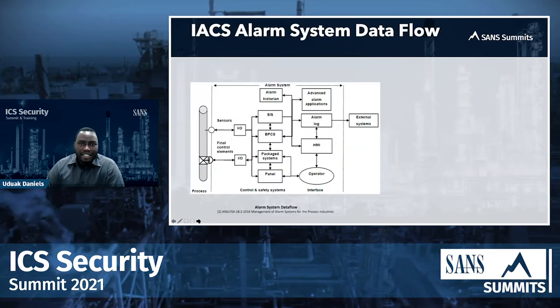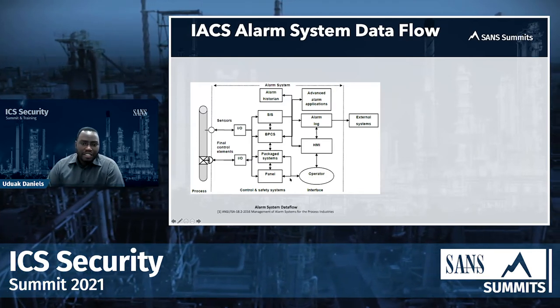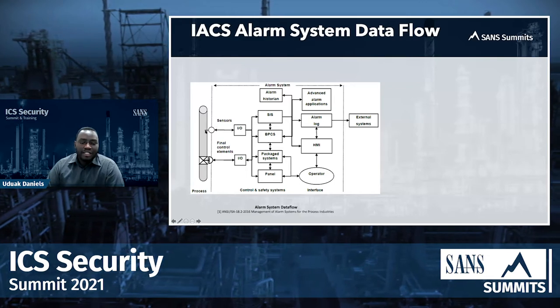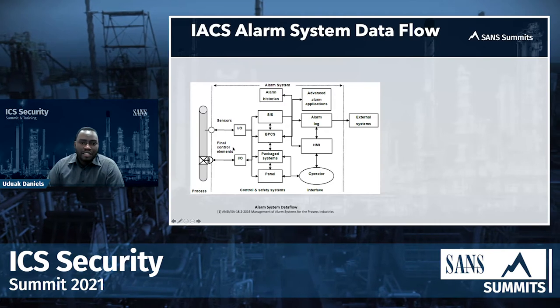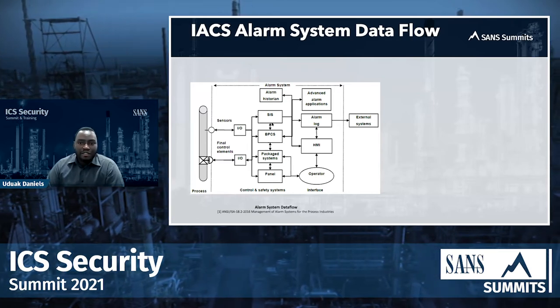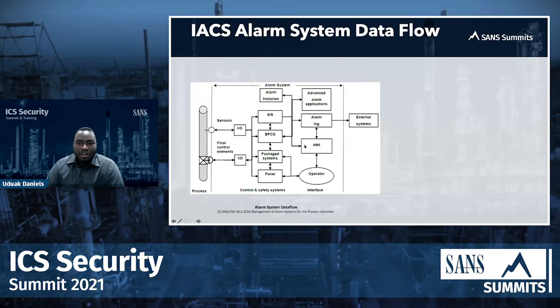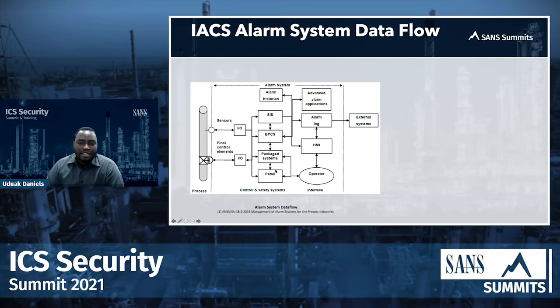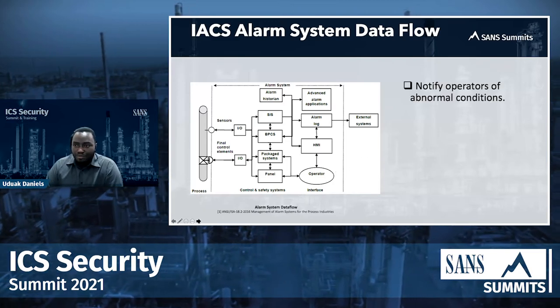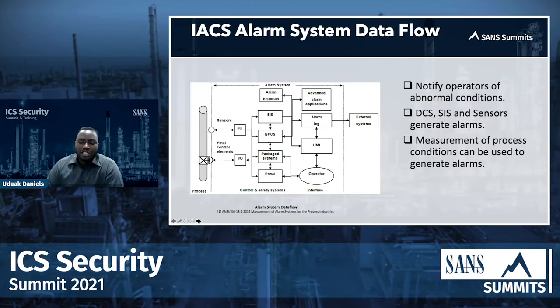Looking at the ICS alarm system data flow from the ISA 18.2 standard: the model shows how an alarm flows from the process layer through sensors into DCS systems, process automation systems, and PLCs. Historians capture these alarms, you have alarm logs, and HMIs allow operators to see what's going on. In some cases package systems have panels that display alarms without going to an operator HMI workstation. DCS, SIS and sensors generate alarms, and measurement of process conditions can be used to generate alarms.